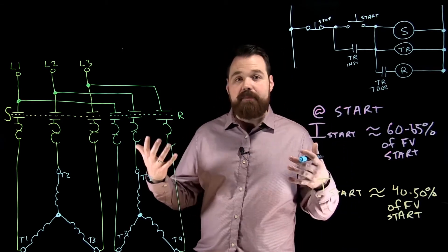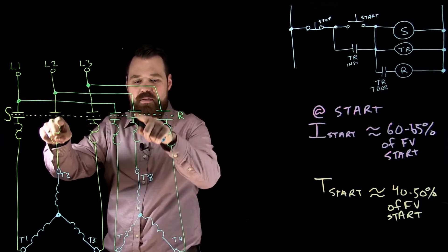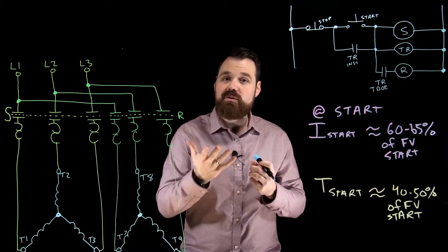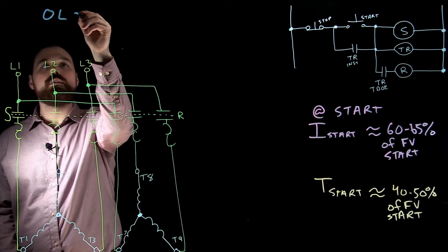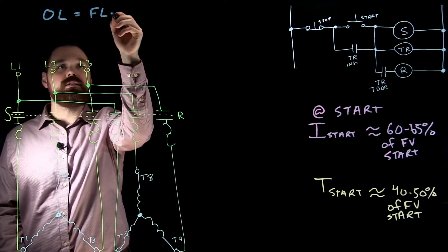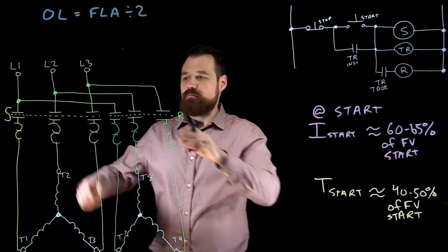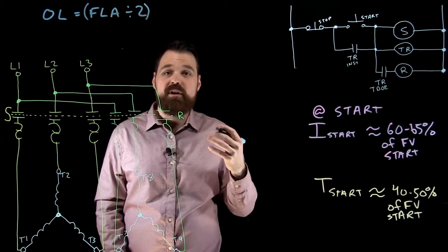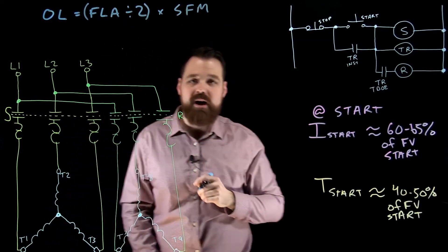So basically, when we look at this, if I'm current and I come down line two, I'm splitting into two and then going through two separate overloads. So in order to size our overloads, what we are going to do is we're going to take our FLA, our full load current, divide it by two because there's those two paths for current to flow, then we're going to multiply it by whatever our service factor multiplier is.